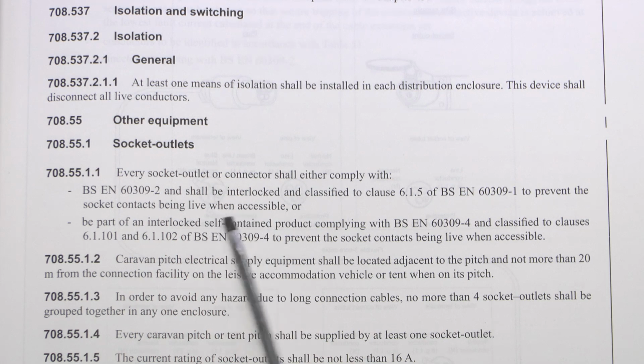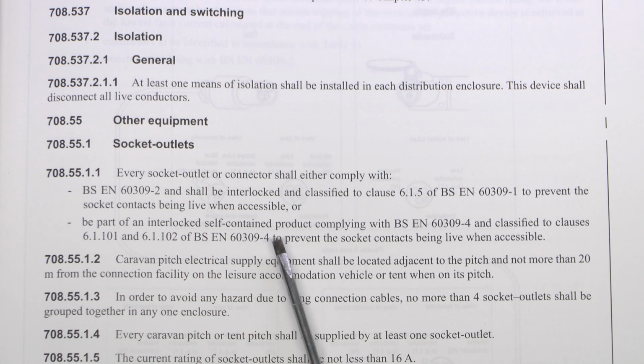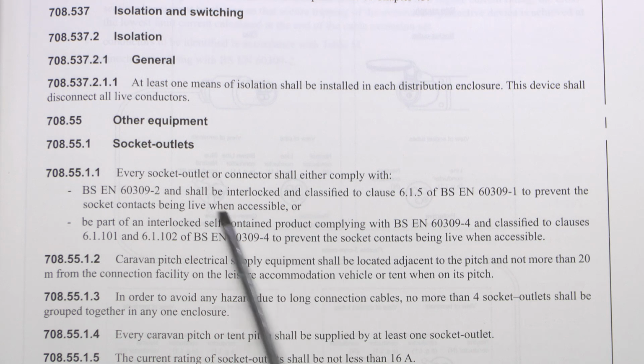And as it says here, the point of that is to prevent the socket contacts being live when accessible, because that type of socket does not have shutters on the actual socket tubes. So if it was turned on and there was no plug installed, it would be possible to poke objects in there and obviously receive an electric shock from that. So interlocked sockets are now required on all caravan pitch supplies, and it says here can either be a single product or one that's part of a self-contained system, as is more usually supplied there.